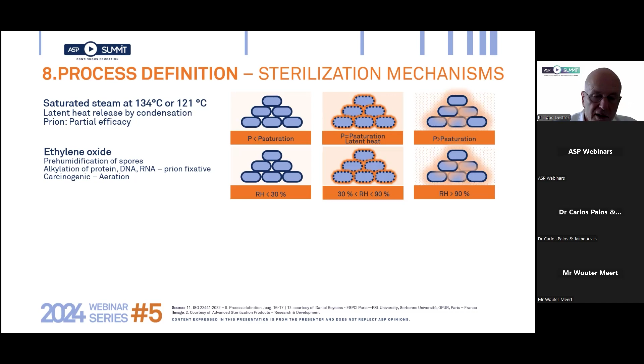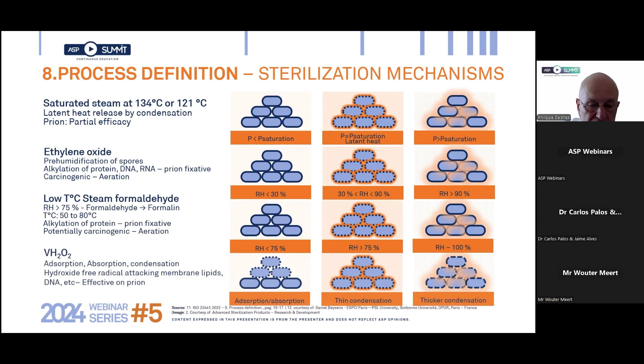So let's stay there for the moment. Sterilization processes are in fact much more complex than people tend to think. Steam, for example, is not just saturated steam. What makes steam so efficient is the release of latent heat when saturated steam condenses on device surfaces. Ethylene oxide needs condensation to penetrate the spore membrane. Ethylene oxide is a very penetrative gas, but it's not able to cross the membrane of spores. Formaldehyde must be converted into liquid formaldehyde to become efficient. Gaseous formaldehyde is not efficient on germs. And the H2O2 process proceeds by adsorption, absorption, and optimized condensation.